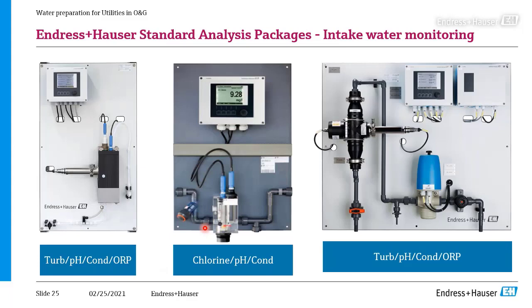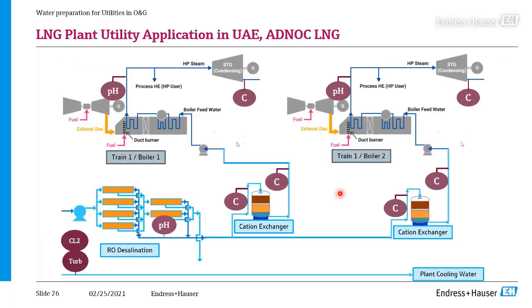Just to give you an idea how these measuring panels can look, I selected three different ones. This is a multiple flow assembly measuring turbidity, pH, conductivity, and ORP in the makeup water, not in the steam cycle. Then there's a chlorine panel with pH compensation and conductivity, and another panel with turbidity, pH, conductivity, and redox potential. So various setups of these panels are possible, and you can buy them ready-made from Endress Hauser, no problem.